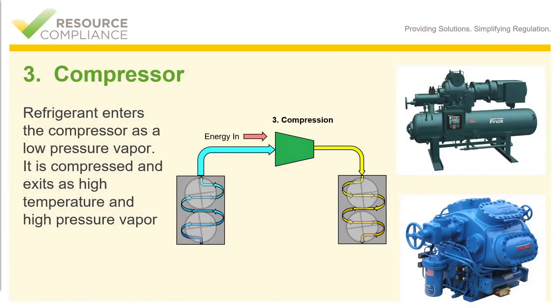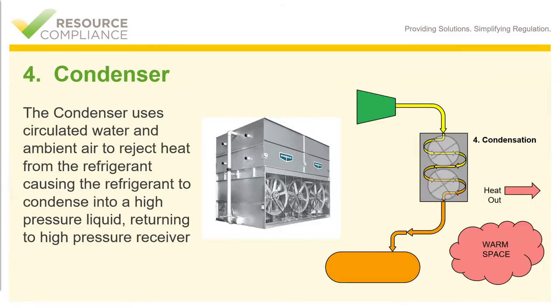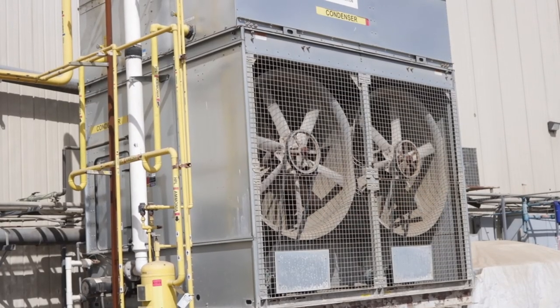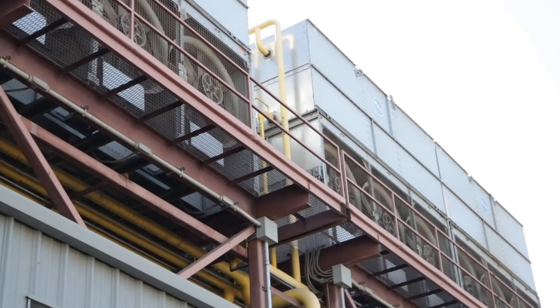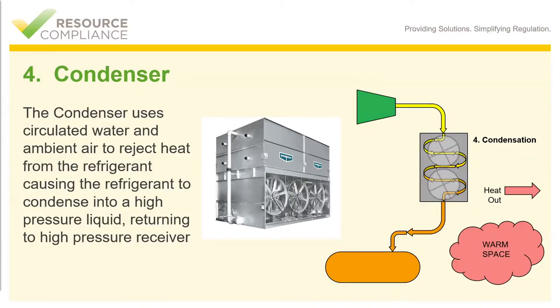After the compressor has raised the low temperature, low pressure vapor to a high temperature, high pressure vapor, in the final stage of the refrigeration cycle we once again see that same principle at work. Heat energy always moves from a warmer space or object to a colder space or object. Here in stage four, the condenser uses circulated water and/or ambient air to reject the heat from the refrigerant to the outside atmosphere, causing the refrigerant to condense back into a high pressure liquid, and then it returns to the high pressure receiver.